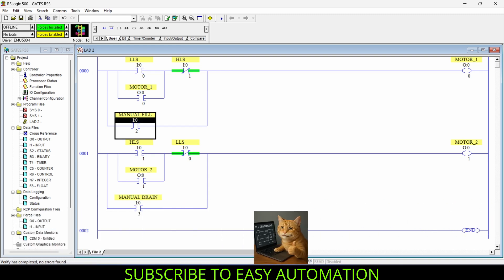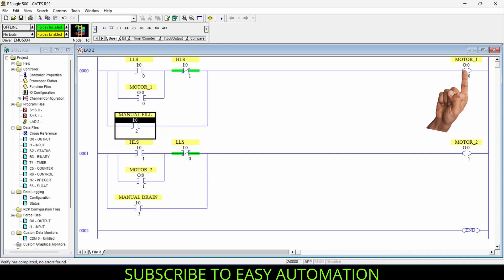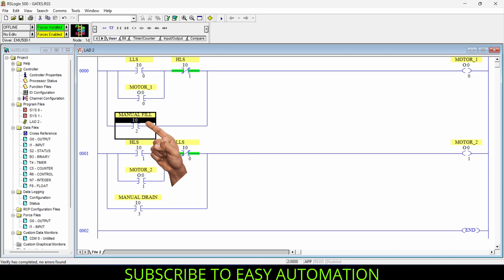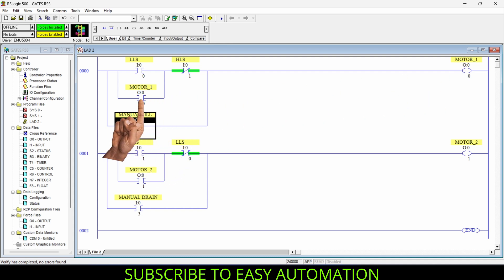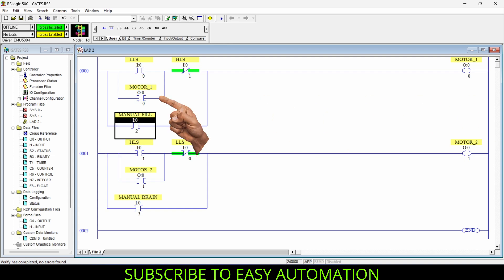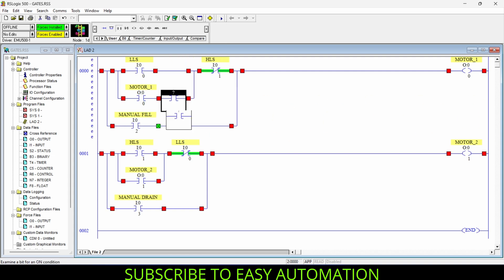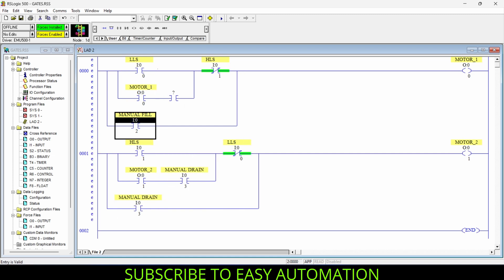There is one problem: when the operator toggles the manual switch, the motor starts and gets held by the holding contact, so toggling the manual switch off won't stop the motor because the holding circuit keeps supplying it. To break this hold, I'll add one NC contact in each rung and copy the Manual Fill and Manual Drain addresses to these NC contacts respectively.